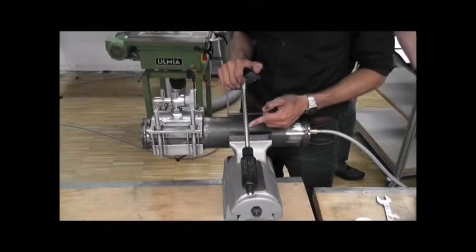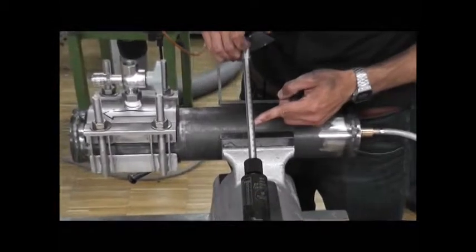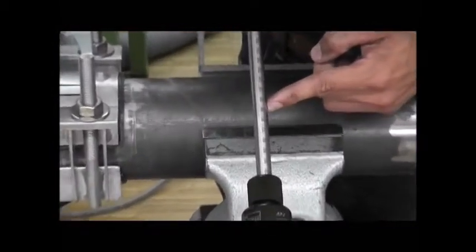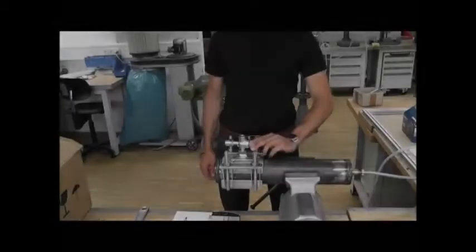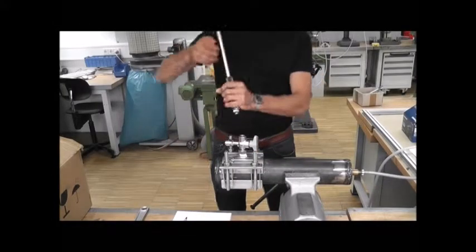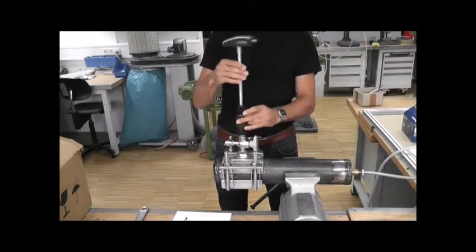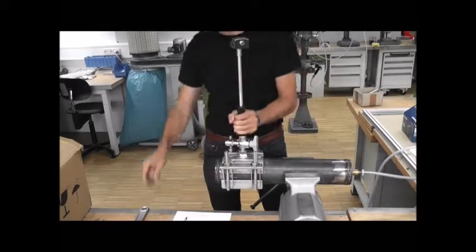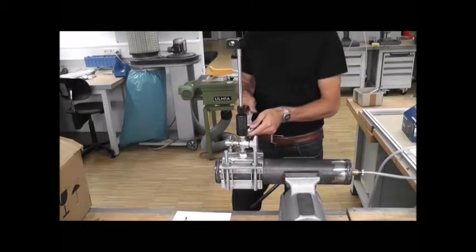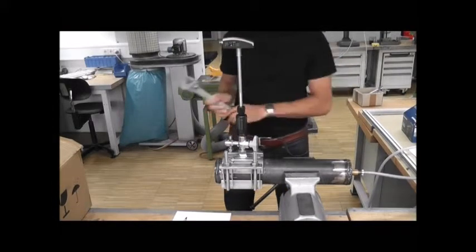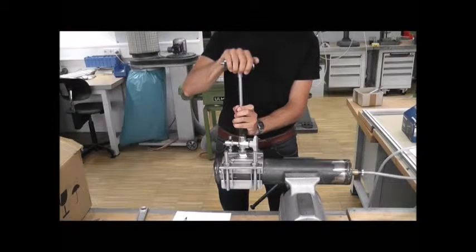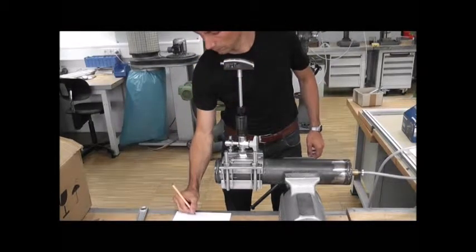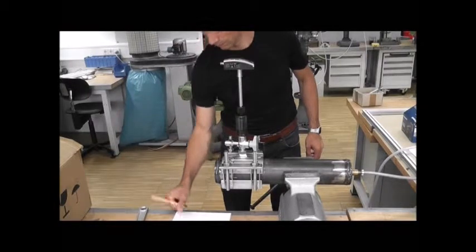The reason why we have to install the 6448 before drilling the hole is that we need to know the value on the scale when the transmitter bears on the top of the pipe. We need this value afterwards during the transmitter installation to adjust the probe to the middle of the pipe. To do that, first make sure the ball valve is opened. Second, screw the transmitter on the ball valve and tighten it with a wrench. Third, press the transmitter to the end limit. Fourth, read and notate the value on the scale.